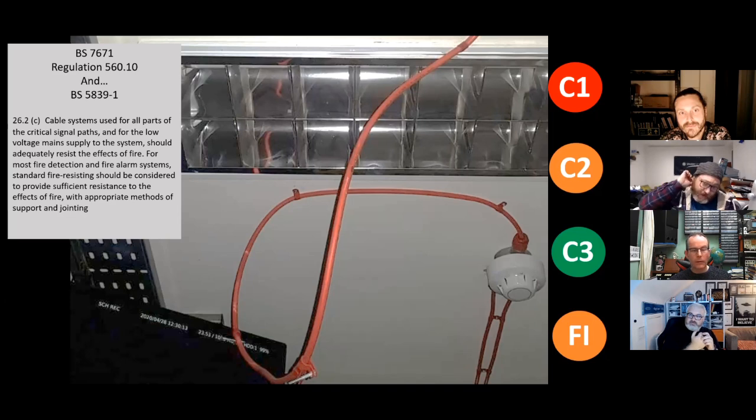Yes. So just to say, I've come up with three different codes here because I need to know more. Dan's done the same. And we would easily go to a code breaker or share it with people, but we need to collect as much info as we can for us all to be able to get our engineering judgment across. And an image can be seen in many different ways if we don't have the confidence to interpret what we see. Now, Dan's offered information to me that I didn't understand, and that's changed my C2 to a potential C1. So context and understanding of risk is really important.